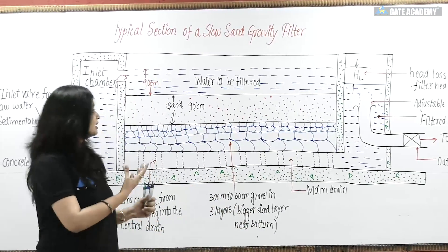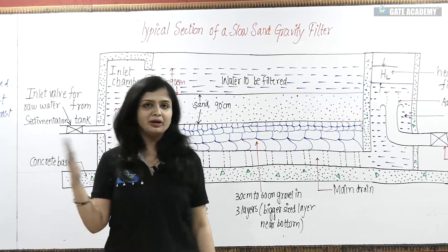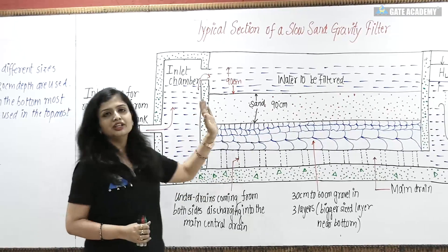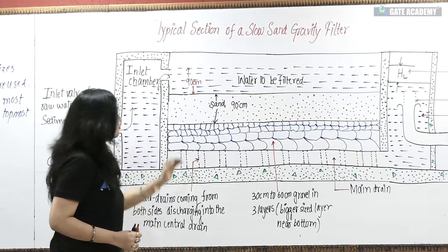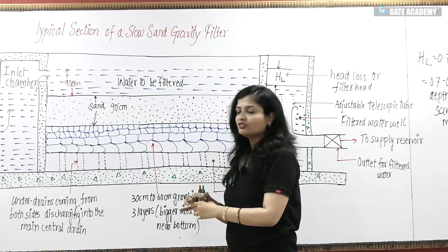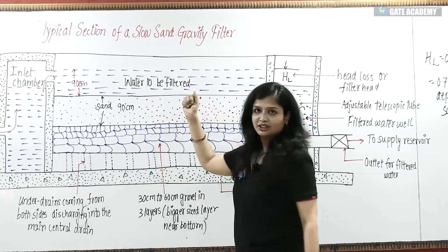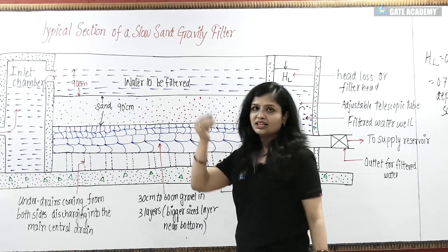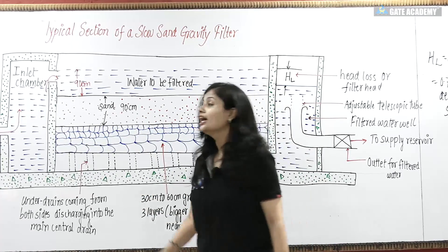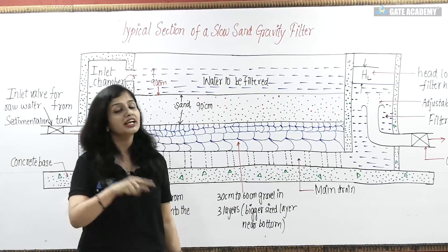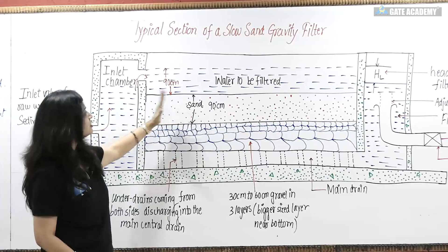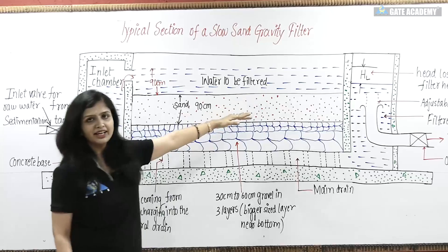For slow sand gravity filters, you don't need back washing. Instead, you remove 1.5 to 3 cm of the top sand layer. Since the finer sand particles are in the topmost layer, there will be more dirt particles and more impurities accumulated there. So you scrape and remove 1.5 to 3 cm of sand, and replace it with fresh finer sand.